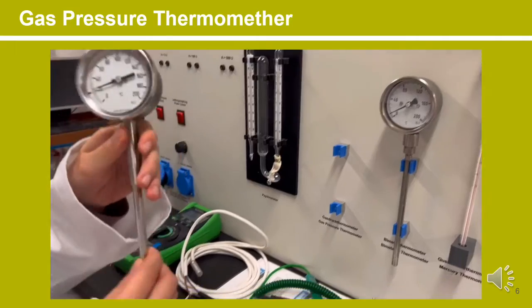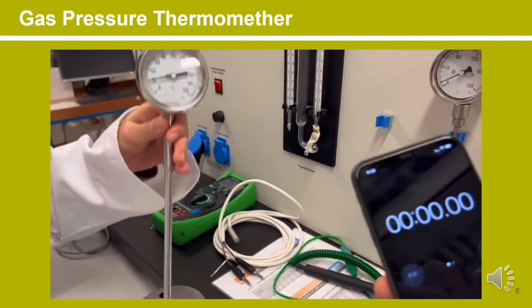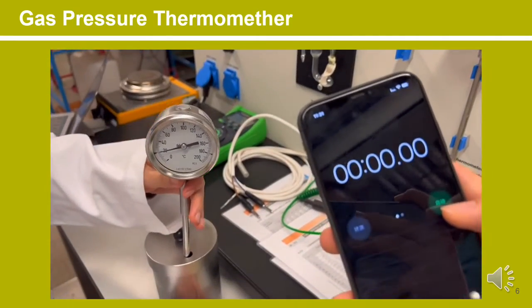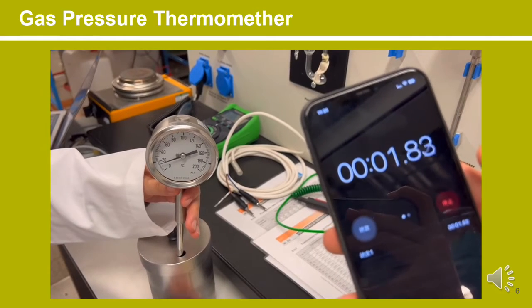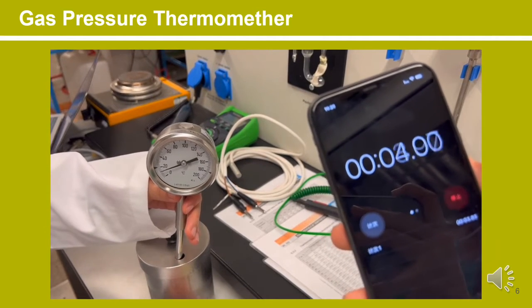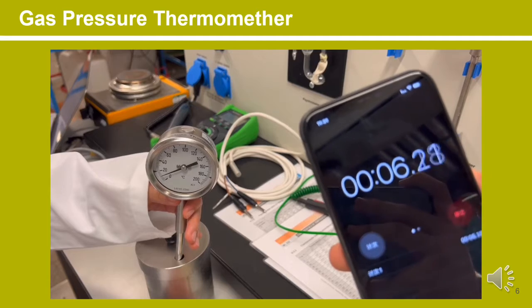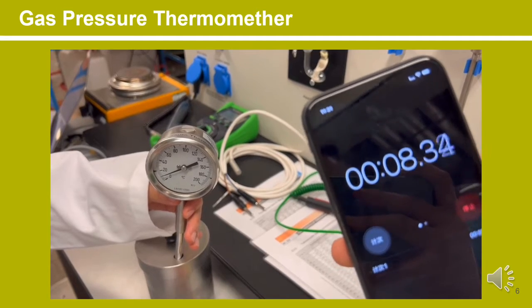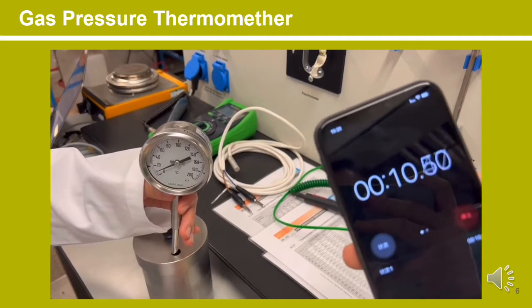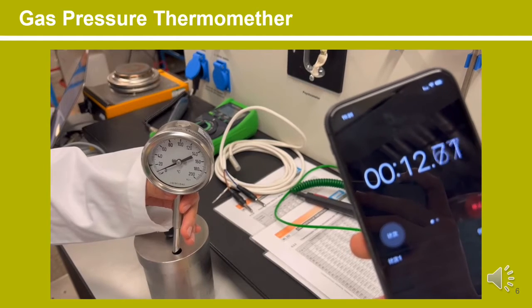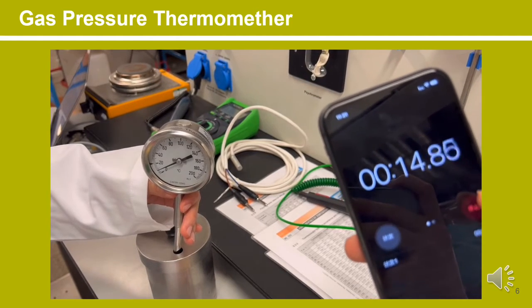Gas pressure thermometer works on the principle that the volume of a gas increases when the temperature of the gas increases. A temperature variation acting on the sensor proportionately alters the pressure of the gas contained within it. It has a wide range of measurement possible, from negative 260 degrees Celsius to 800 degrees Celsius, so it can be used in extreme environments like the furnace.